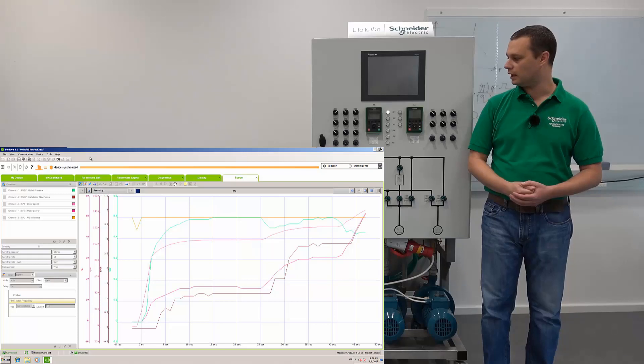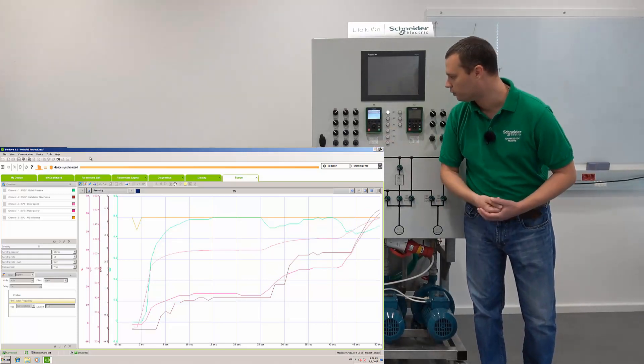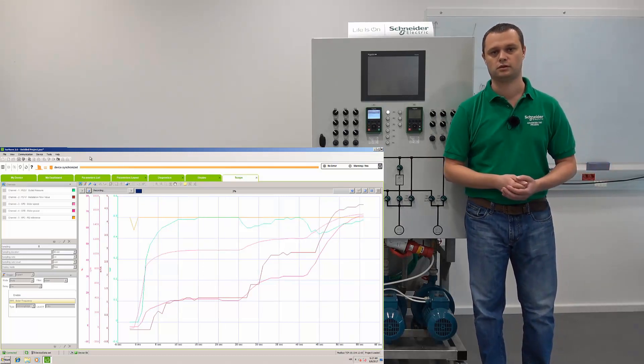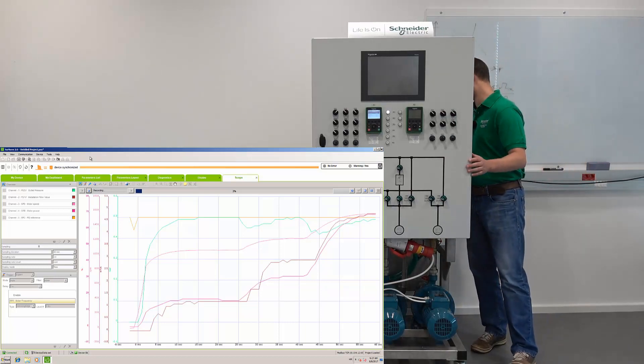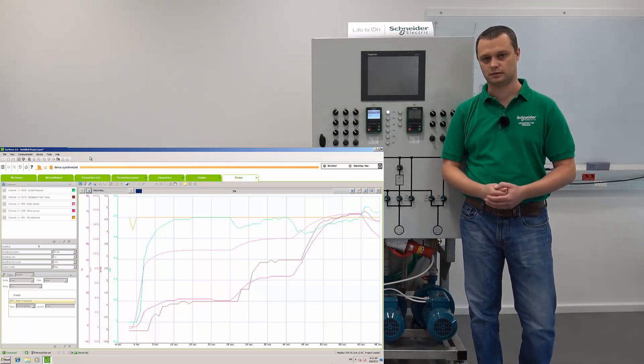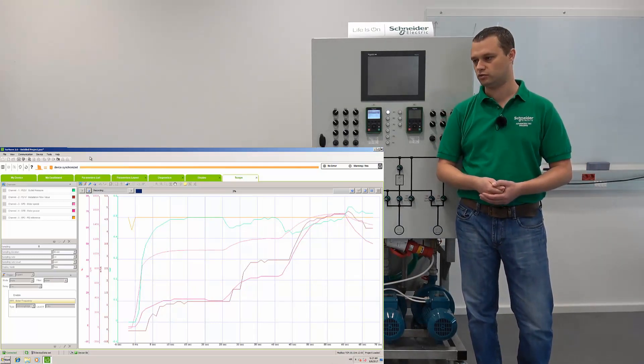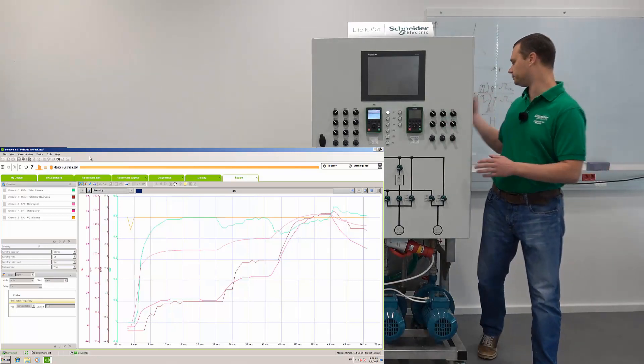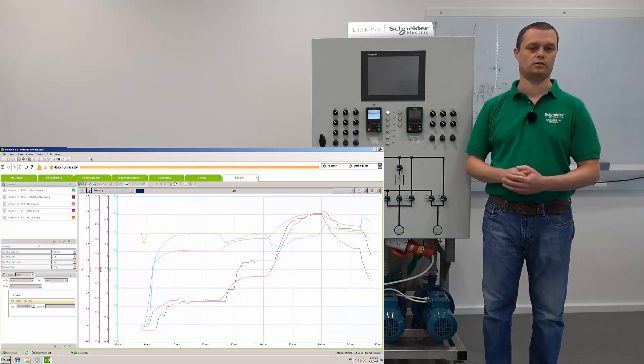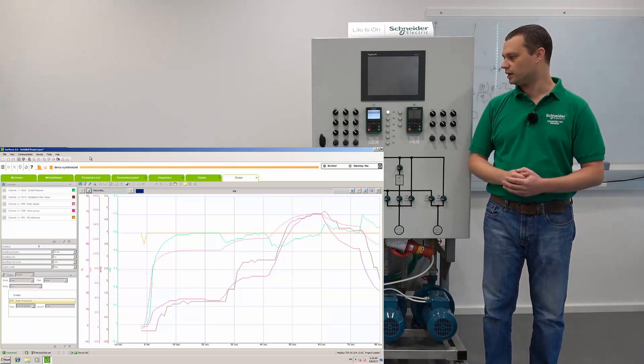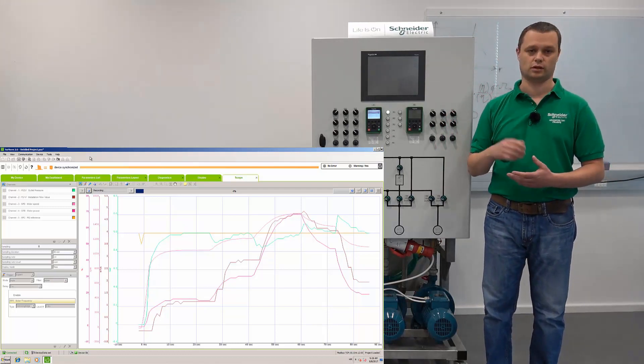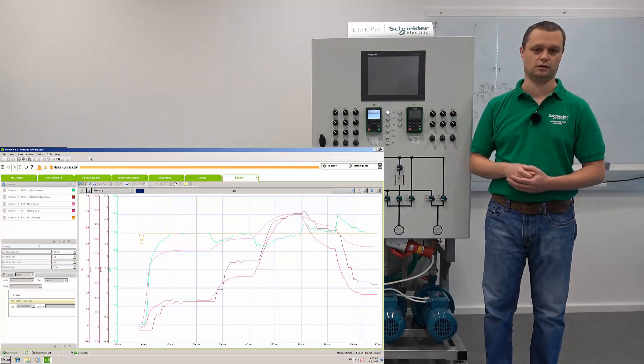Flow continues to go up and the drive is slowly moving towards the high speed limit. Now let's try to reduce the flow. We see a slight peak in pressure, flow is going down, but the drive is maintaining the pressure again. The drive is going down in speed — we can see it is really keeping the pressure level and doing its best according to the PID settings of proportional and integral gain.